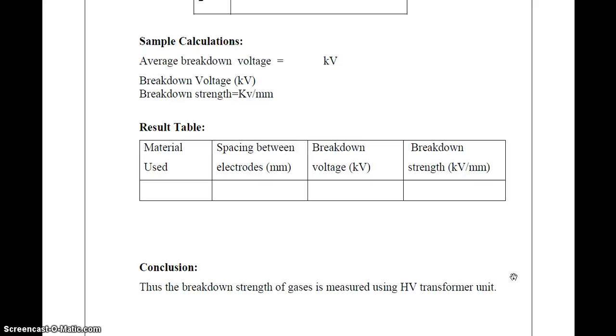Then the breakdown strength of gaseous dielectric material depends on various factors. First one is gap length, second is geometry and material of the electrode, then uniformity and treatment of the surface, then presence of extraneous particles, gas pressure, then magnitude of applied voltage, then frequency of applied field, then chemical composition of gases. Then the breakdown strength of gases widely depends on the dielectric strength of the material, breakdown voltage and spacing between the two electrodes. Then the breakdown strength concept depends on conditions like temperature, applied voltage, frequency and type of electrode, that is, uniform electrode or non-uniform electrode.